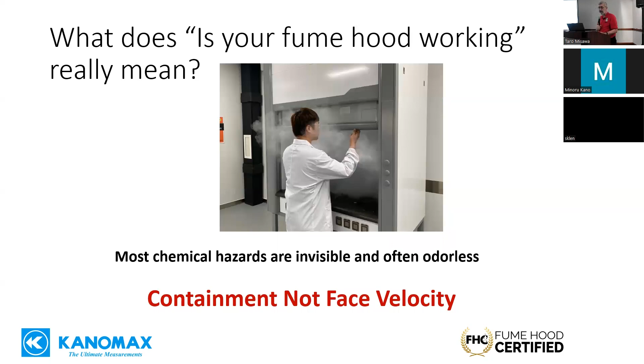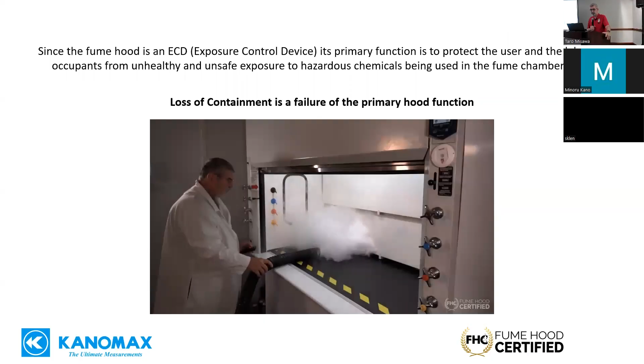So what does your fume hood working really mean? Unfortunately, and we'll get into it, there's a misconception over the difference between face velocity and containment. Since the fume hood is an exposure control device, its primary function is to protect the user and the lab occupants from unhealthy and unsafe exposure to hazardous chemicals being used in the hood. So loss of containment is a failure of the primary function of the fume hood.